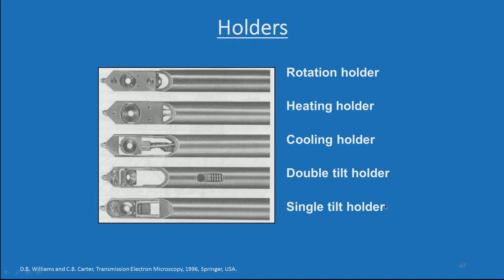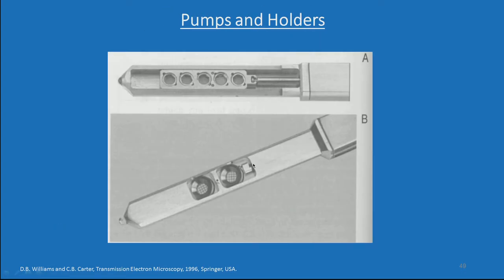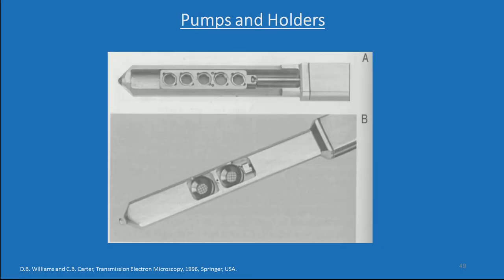It is not that only a small sample size can be kept — you can also have bigger samples more than 3 mm. You can simultaneously load samples in a multi-sample holder inside the vacuum, or put them in a two-slot holder. These are some of the varieties of holders available with each microscope.